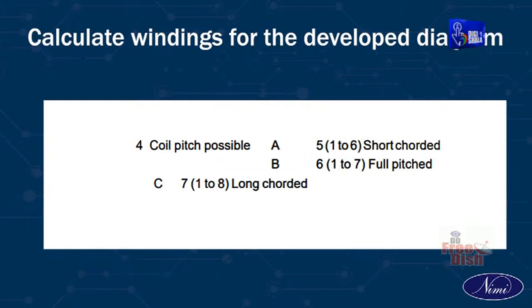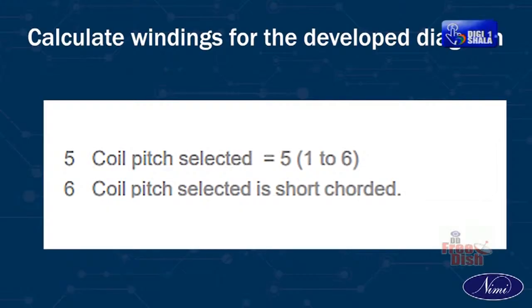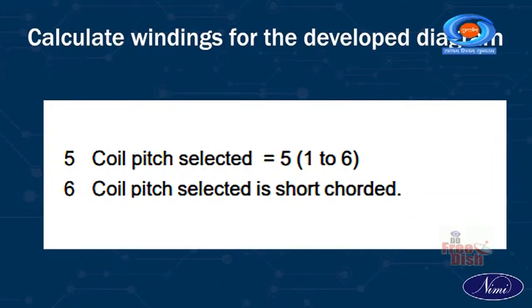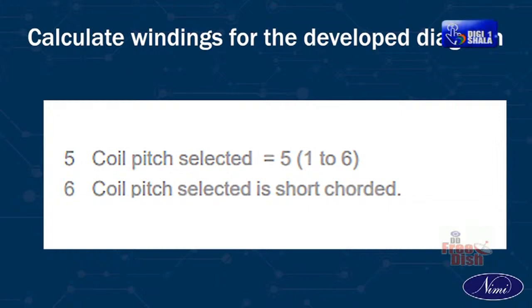4. Coil pitch possible: A. 1 to 6, short chorded. B. 1 to 7, full pitched. C. 1 to 8, long chorded. 5. Coil pitch selected equals 1 to 6, coil pitch selected is short chorded.